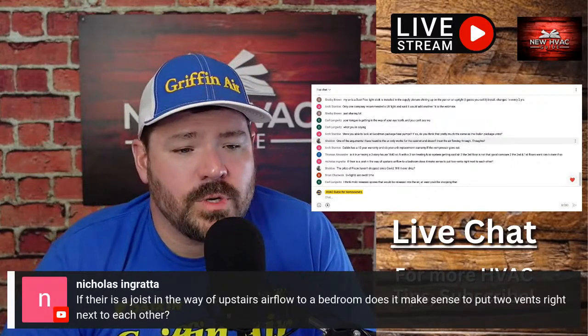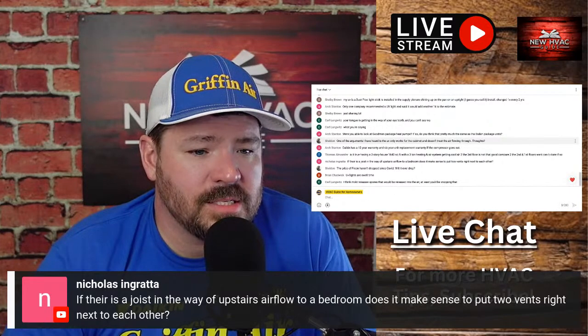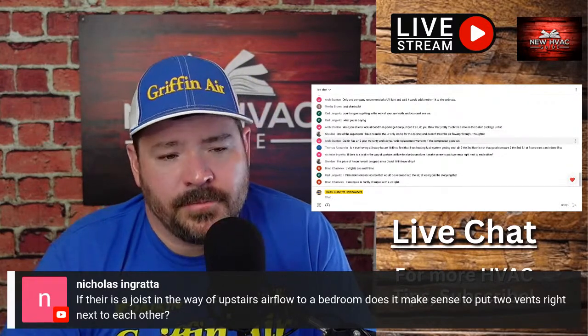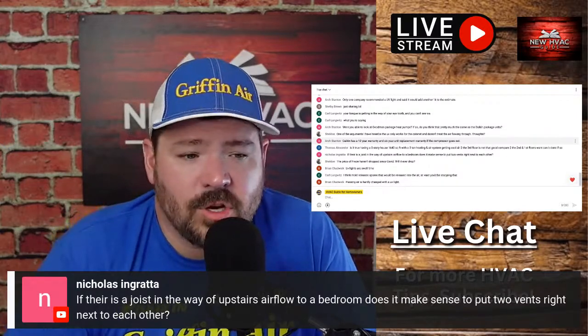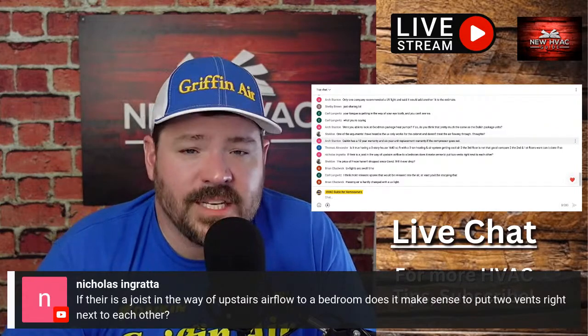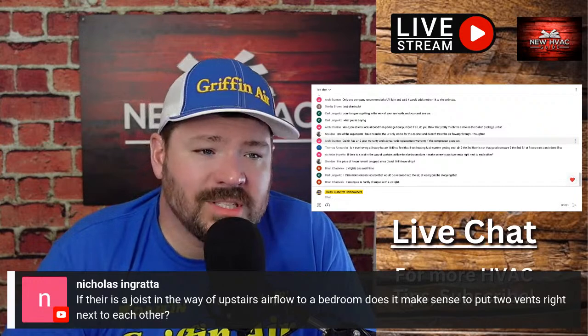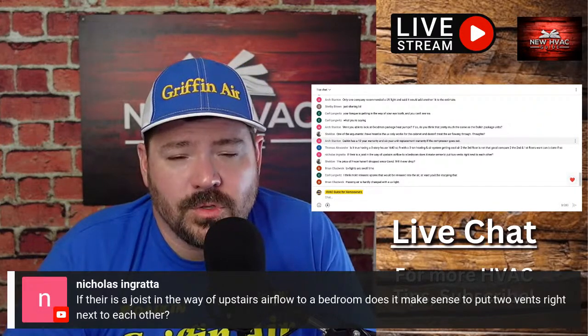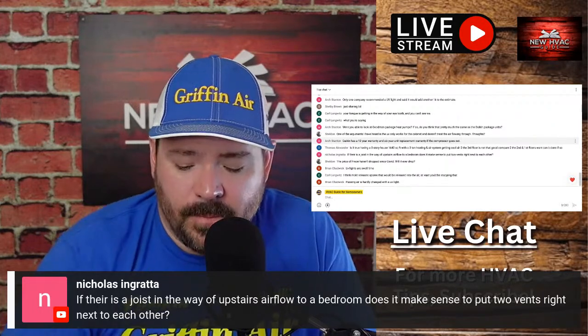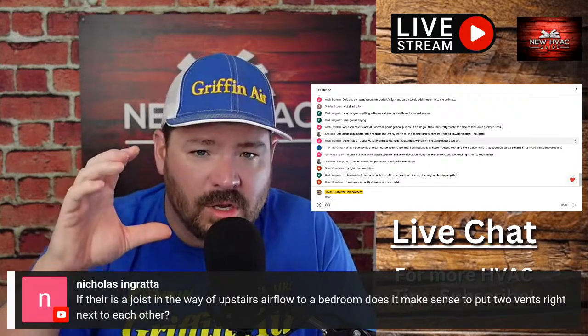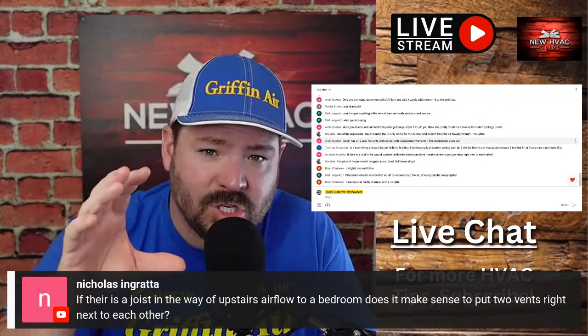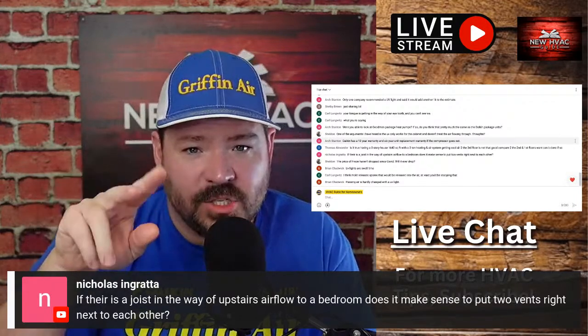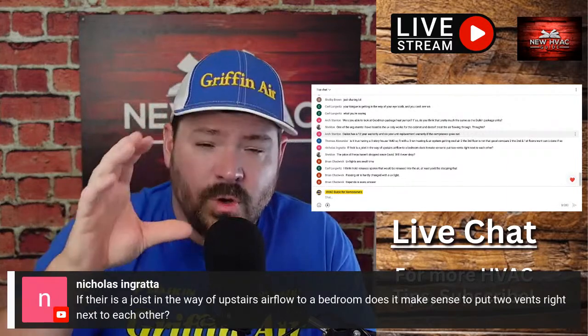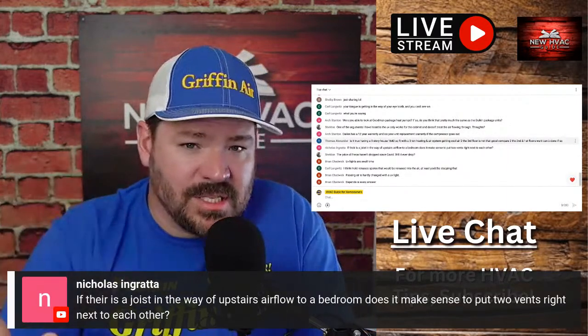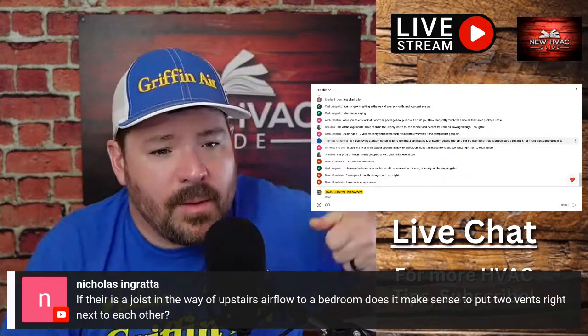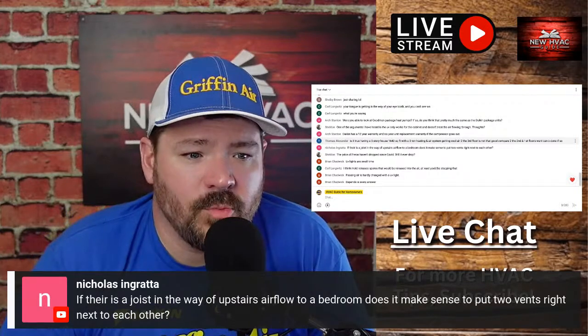Nicholas asks, if there's a joist in the way of the upstairs airflow to a bedroom, does it make sense to put 2 vents right next to each other? It's hard to answer definitively, but I've seen that done before, or you size it bigger than you normally would. For example, 2 6-inch round ducts are roughly equivalent to one 8-inch round duct for a supply, 2 6-inch ones give about 100 CFM each, and an 8-inch gives about 200 CFM. So you might run an 8-inch instead of a 6-inch to that space because a joist is in the way and you can't fit another vent in that room.